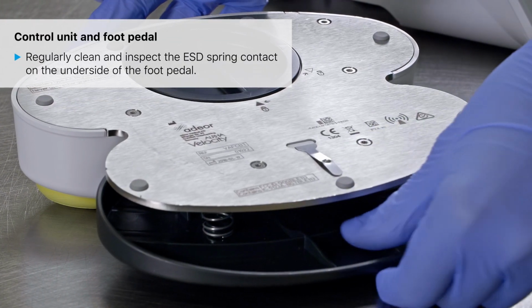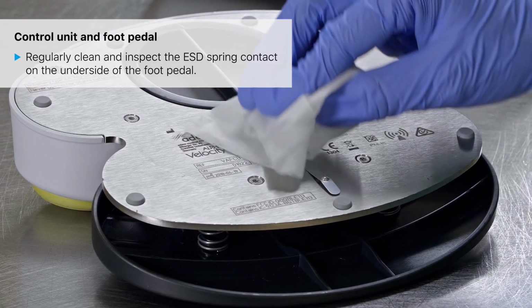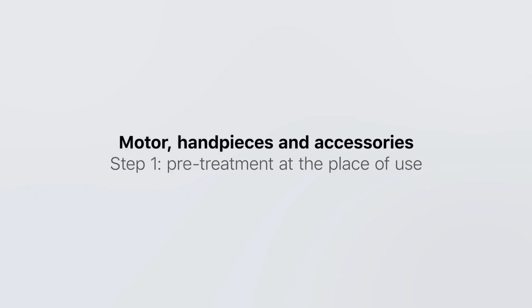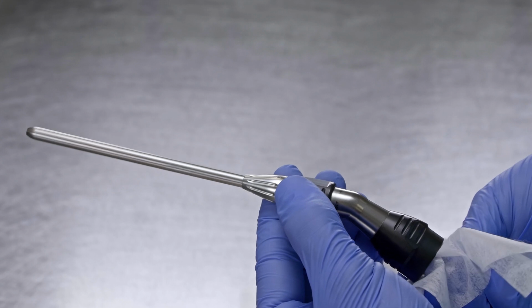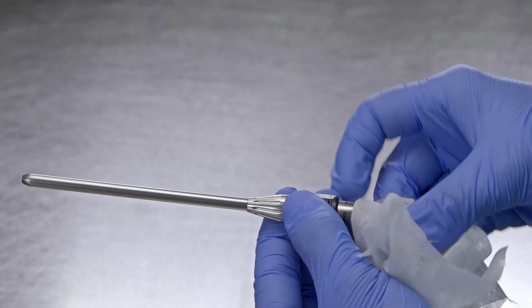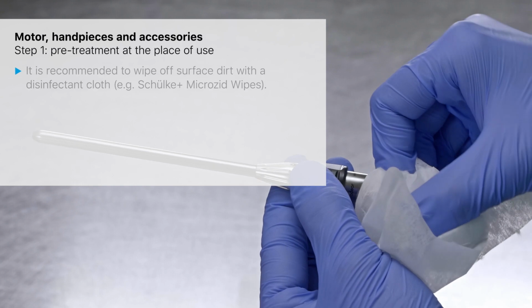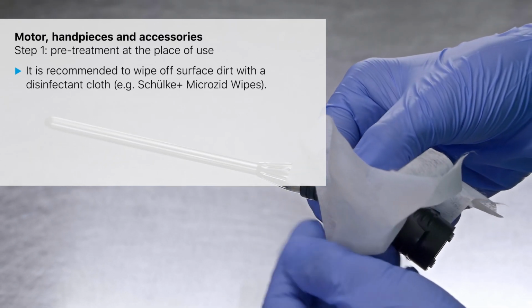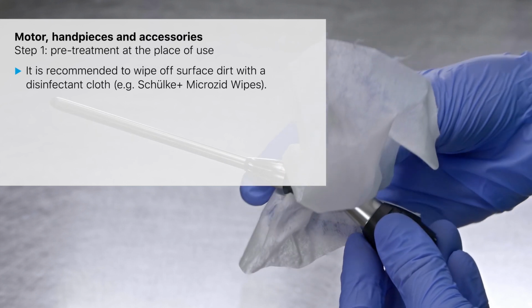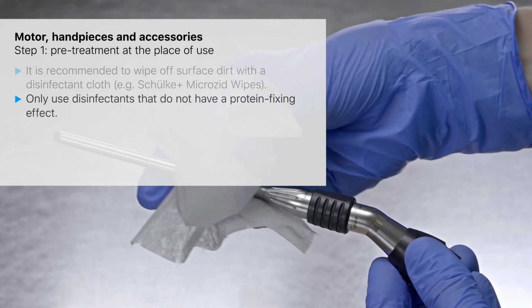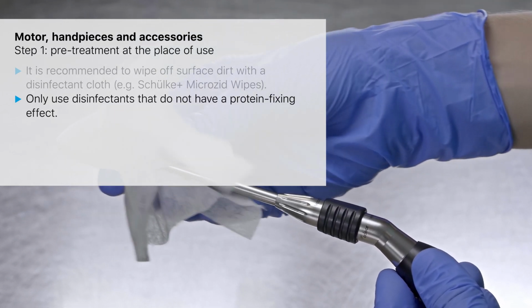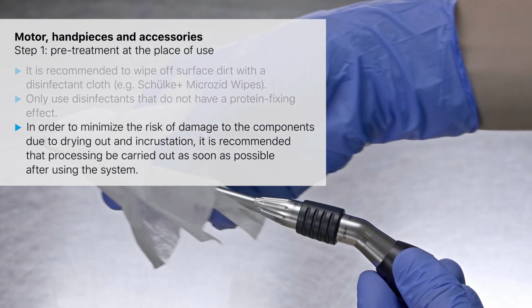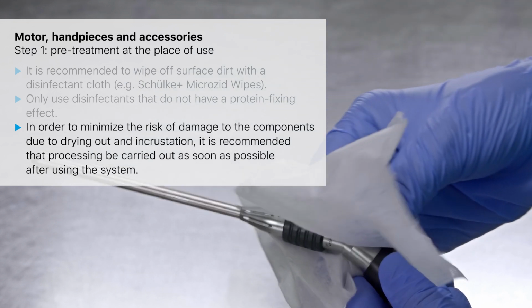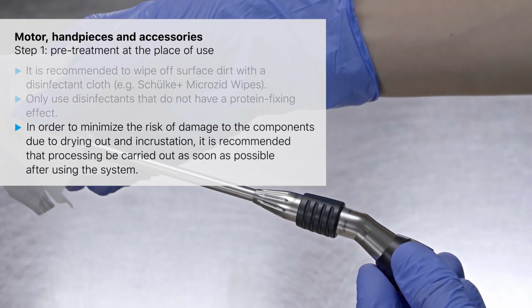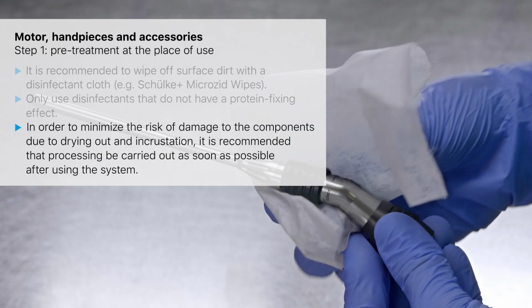Regularly clean and inspect the ESD spring contact on the underside of the foot pedal. It is recommended to wipe off surface dirt with a disinfectant cloth, e.g. Schülke Microzid wipes. Only use disinfectants that do not have a protein fixing effect. In order to minimize the risk of damage to the components due to drying out and incrustation, it is recommended that processing be carried out as soon as possible after using the system.